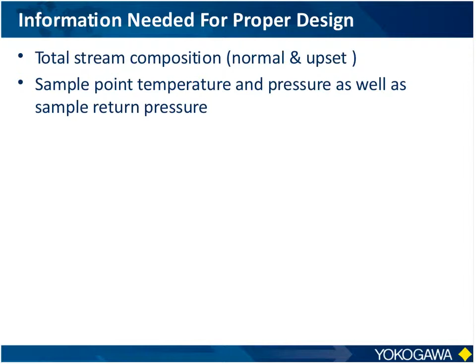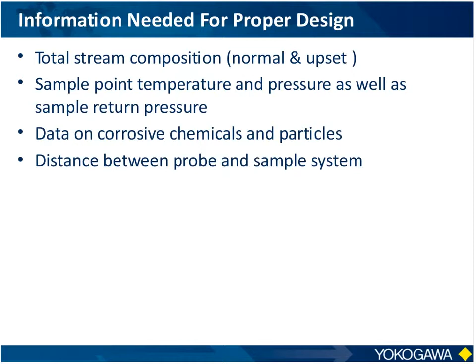I need to know the sample point temperature and pressure so I can extract the sample properly, and what the return pressure and temperature is where I'm bringing the sample back to. I also need information on any corrosives or particles, and the distances between the sample point and the shelter, otherwise I can't accurately calculate the lag time to make sure the flows are correct.